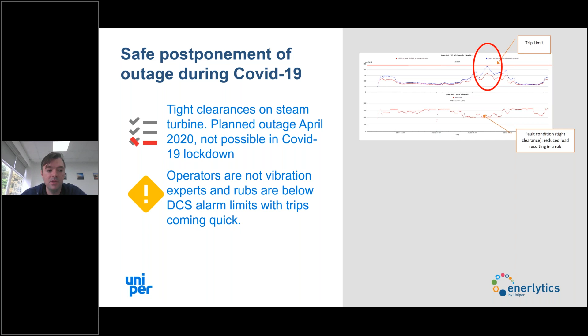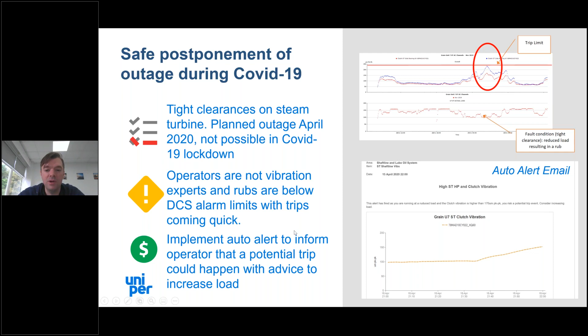So we created auto alerts based on the data which was sent to the control room for the team to act way before this acceleration of a problem happens. And it's saying here the alert's fired, so because they're running at reduced load, consider increasing your load to just manage the current situation and then bring it back down to the reduced load. And that's really important in this market because the unit's running at minimum load because that's where the money is. And if they're to come off, the fines for basically increasing instability of the grid are extremely high, whereas the fines for overgeneration are very small in this case. So in terms of a risk-benefit analysis, this was a safe thing to do and enabled the asset to continue to make money until mid-May, when we then completed the outage.